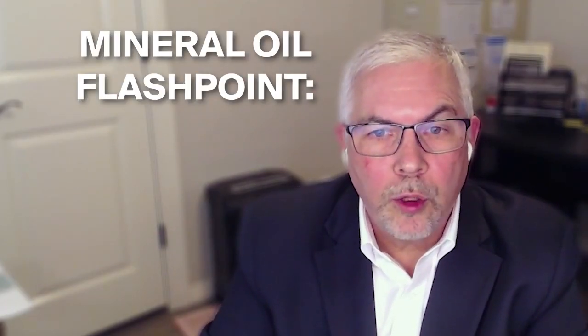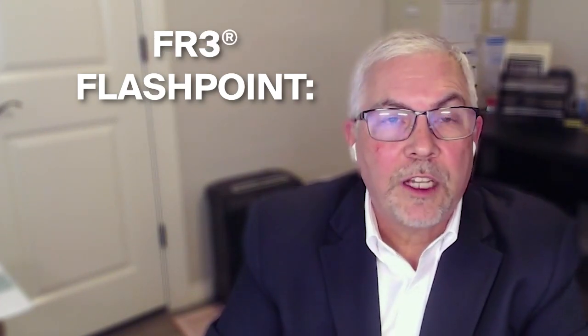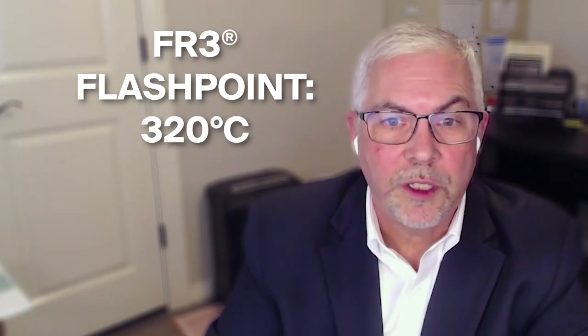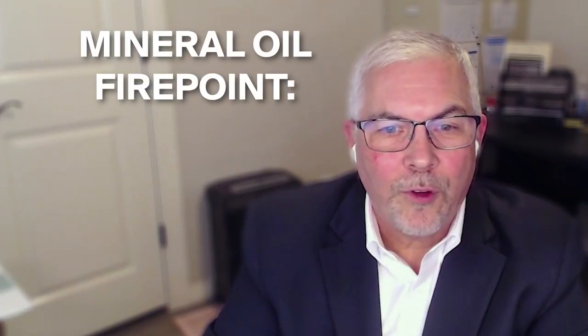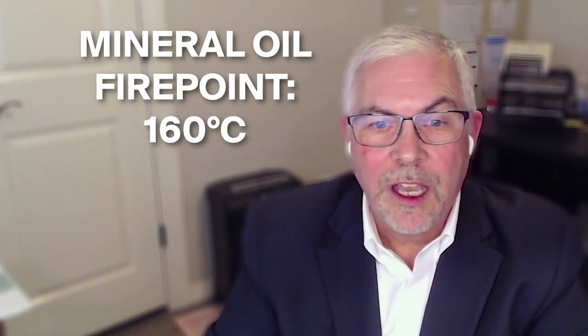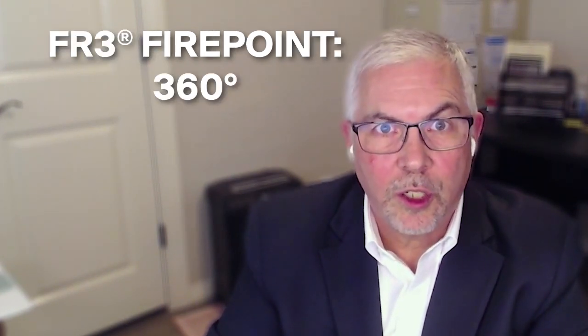That's the flash point. The step beyond that is the fire point, and that's the same basic procedure, except when it flashes, it actually sustains a flame for, I think it's 5 seconds or something like that. The flash point for mineral oil is about 140 degrees Celsius. The flash point for FR3 is around 320 degrees Celsius. More importantly, I think, is that fire point. The fire point for mineral oil is around 160 degrees Celsius, and for FR3, it's around 360 degrees Celsius. So if the fire point is above 300 degrees Celsius, the liquid is considered a K-class liquid, a less flammable liquid, and that's where FR3 falls.